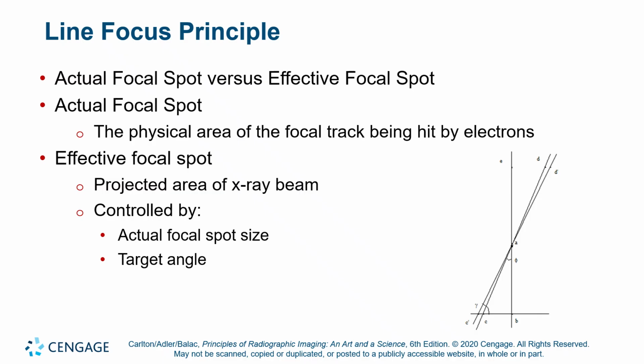Now in my trig proof, basically, as angle C prime AB changes to angle CAB, that top angle theta gets smaller, both the actual focal spot and the effective focal spot also get smaller. So a steeper bevel makes for a smaller focal spot size. The larger the top angle on that right triangle, the larger both focal spot sizes are.